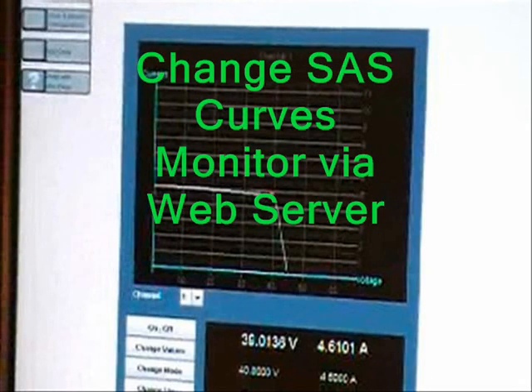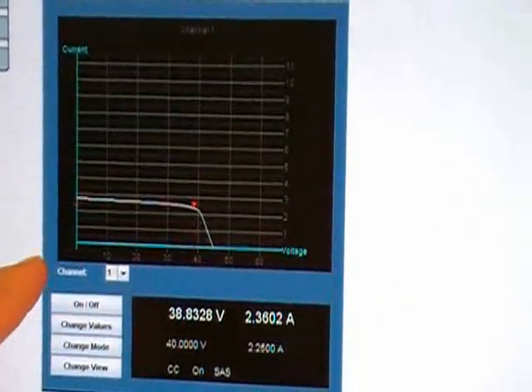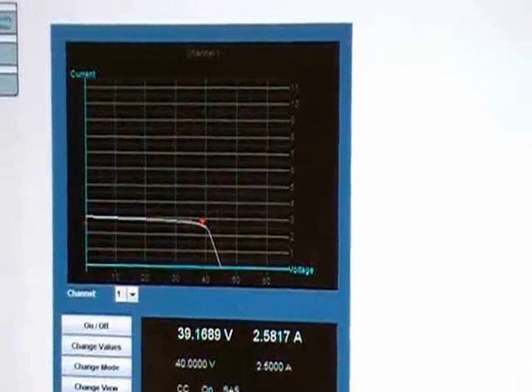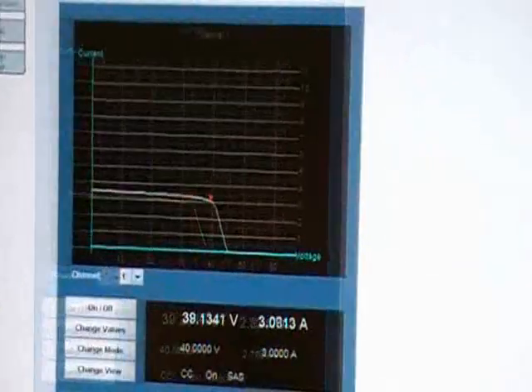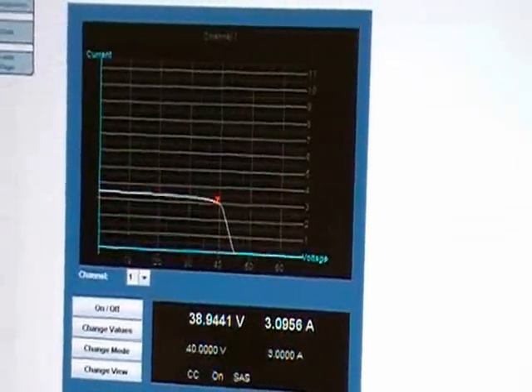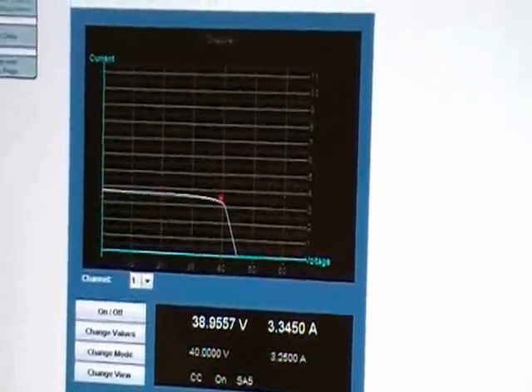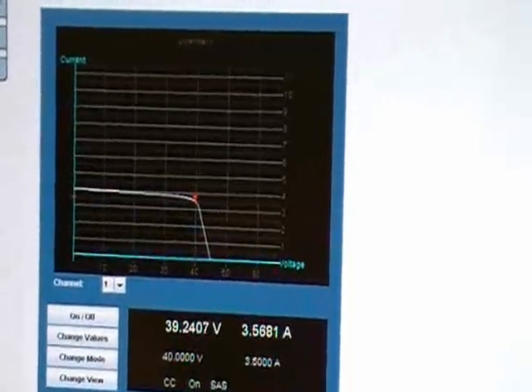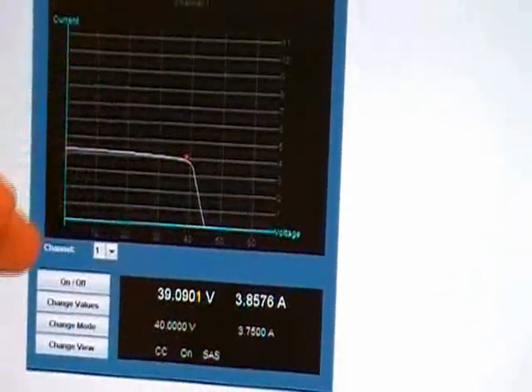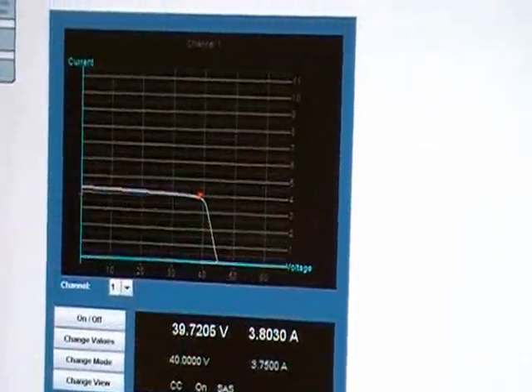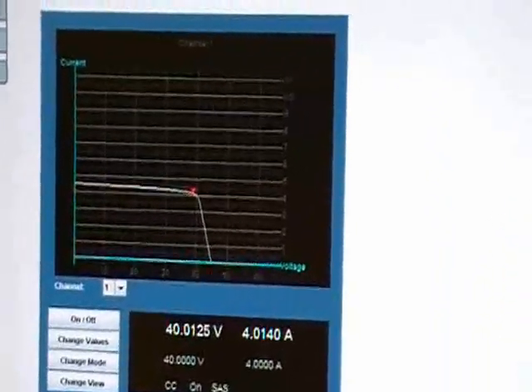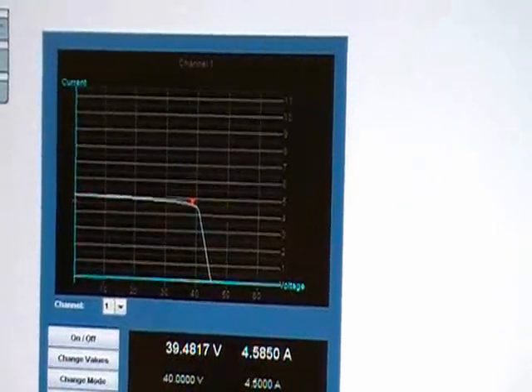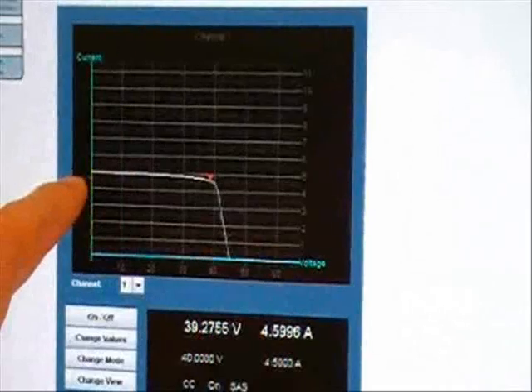With a LAN connection to the Agilent SAS, I can use the built-in web server to monitor the programmed IV curve providing DC input power to the microinverter. Current is shown on the vertical axis and voltage on the horizontal axis. The red triangle indicates the actual output voltage and current of the SAS — the operating point. The maximum power point is at the knee of the curve, and it is the job of the microinverter to keep the operating point at the knee to harvest as much power as possible from a solar panel. As I increase the current of the IV curve simulating more sunlight, the microinverter does a great job of maintaining operation at the maximum power point. At this higher power point, more power is flowing from the microinverter to the light bulbs than from the AC source — meaning in the real world, more energy to the AC load would be coming from the sun instead of from the utility company.